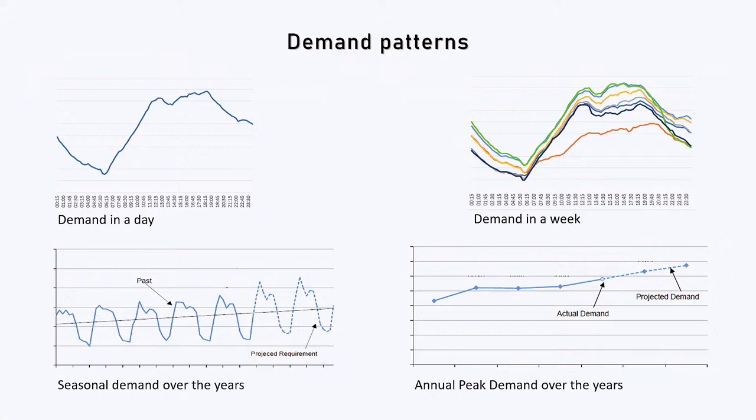Now, this is the demand pattern in any distribution system. It's a daily pattern. During early morning hours, there is a dip. There is one peak during daytime, say at about 11. Then there is an evening peak. This is the standard feature throughout the year. Only in case of peak summer days, say May or early June, we see the peak occurs during afternoon, not in evening, because of air conditioner loads. So this is the pattern.